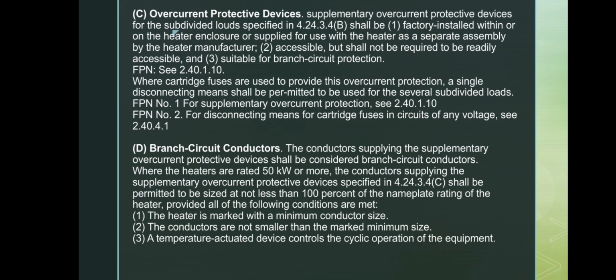Next, the continuous rules for subdivided heating loads. C. Supplementary overcurrent protection devices for subdivided loads. First, the overcurrent devices must be factory installed or supplied by the manufacturer. They must be accessible but not necessarily readily accessible. They must be suitable for branch circuit protection. If cartridge fuses are used, one disconnect may control all the subdivided loads.